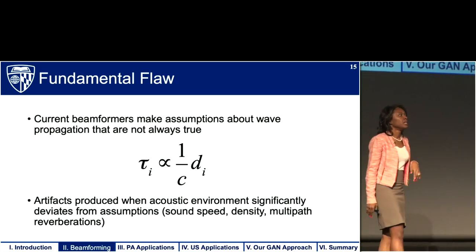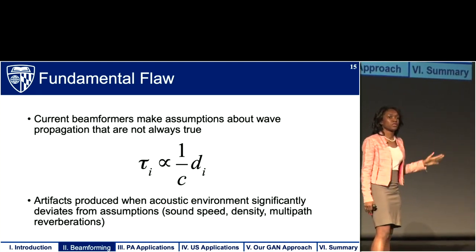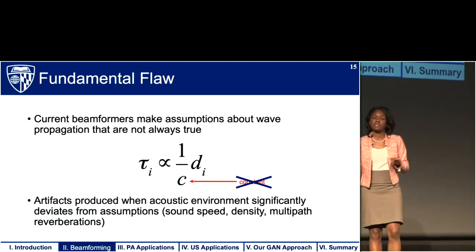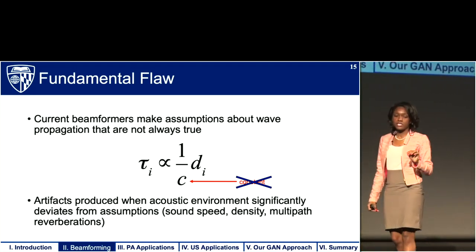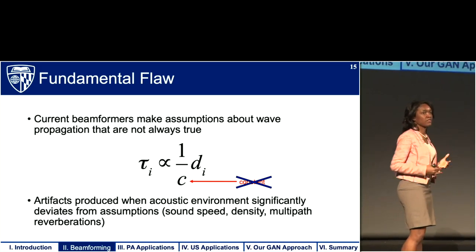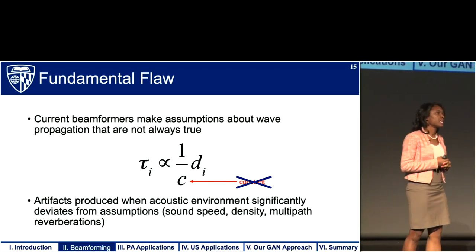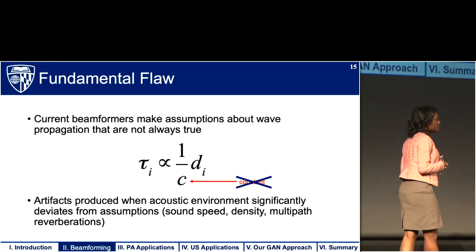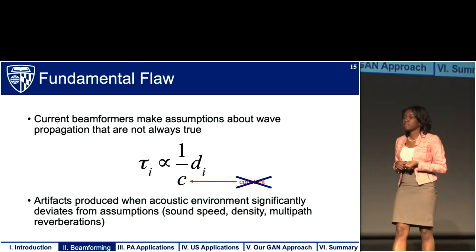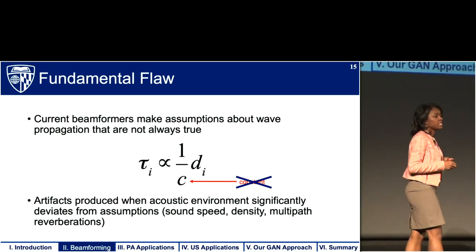This happens because of a fundamental flaw in the beamforming process — current beamformers make assumptions about wave propagation that are not always true. We apply time delays related to the distance from the source to the receiver through the speed of sound, but one assumption is that the speed of sound is constant. In reality, different tissues have different speeds of sound, and the bulk speed of sound within one patient differs from another, producing artifacts when the acoustic environment significantly deviates from these assumptions. This also includes assumptions about constant density and single-path propagation, when in actuality there can be multi-path reverberations or reflections.